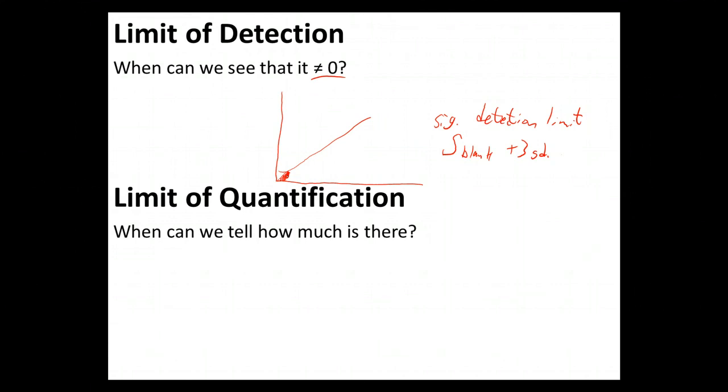Now, when you see the analytical balance go from 0.0000 to 0.0001, do you actually believe that there's that 1/10 of a milligram sitting on the balance that just happened to land and fall back off? No, of course not. You think, okay, that's just some random noise. Which means that you really can't believe it at all if you see that it suddenly turns solid and starts telling you that it's 0.0001 gram. You just aren't going to believe that yet, because you've seen it fluctuating, and so you know this could just be randomness and this could be a tiny bit of drift, though drift is something separate.